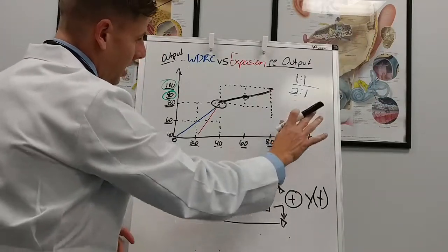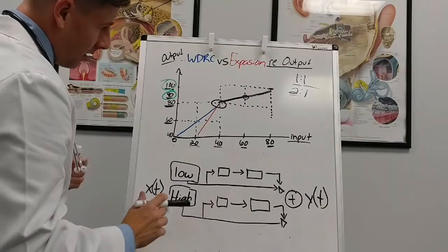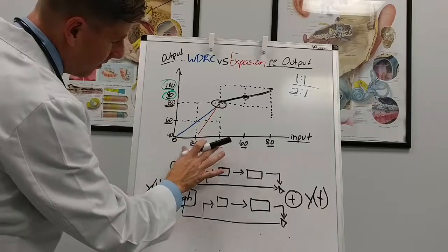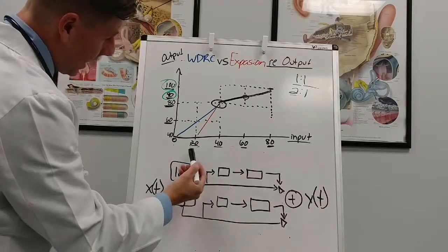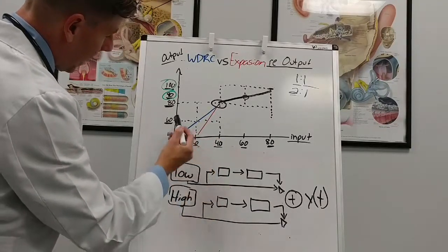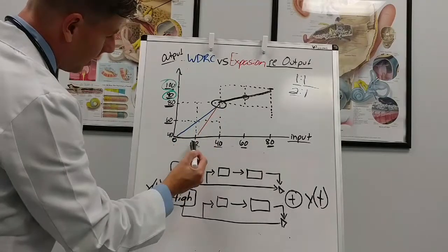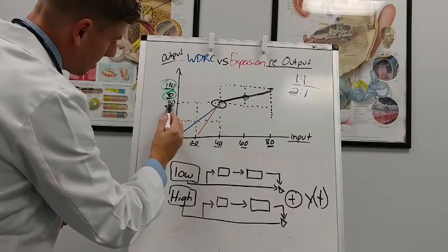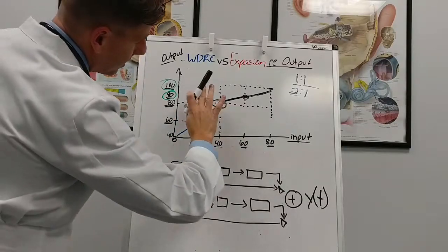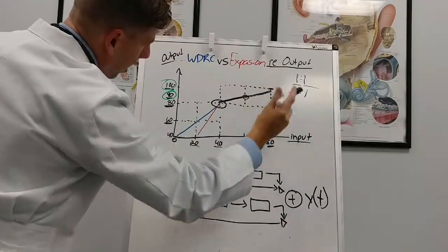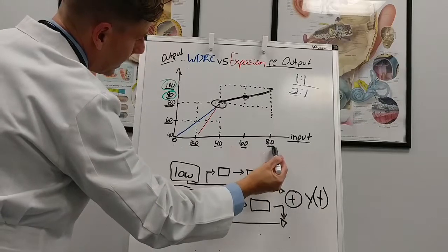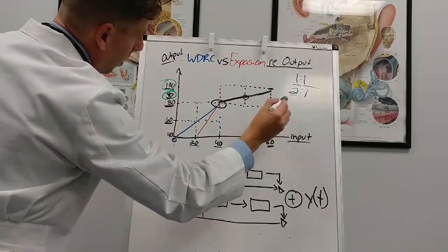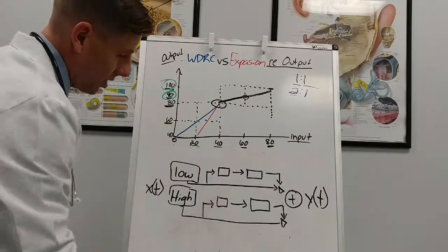And it gets a little bit more complex when we're talking about the gain that we're already using for the hearing aid. Again, here I'm using a 40 decibel hearing aid. So at 20 decibels, I'm going to add 40 because I'm on a 1-to-1. At 40 decibels, I'm going to add 40 because I'm on a 1-to-1, which brings me to 80. But once I start to implement a 2-to-1, it basically means that at 80, I'm no longer going to add 40, I'm going to only add 20. And that brings me to 100.